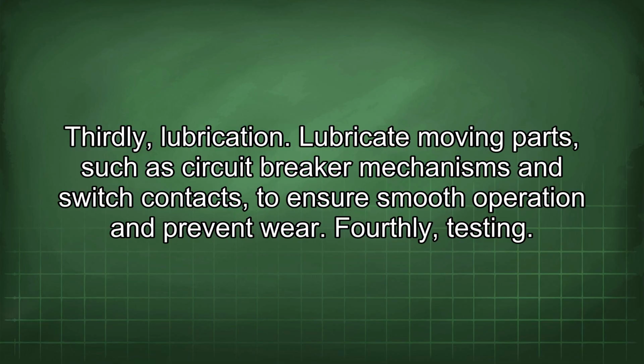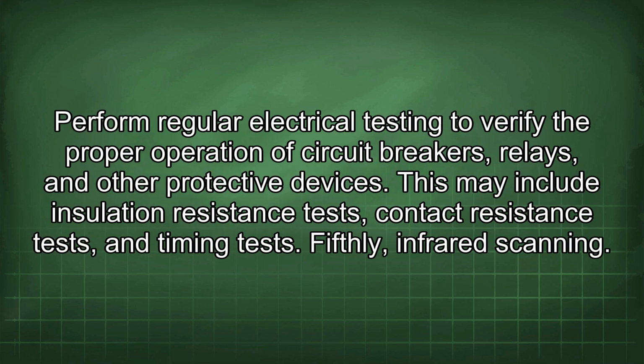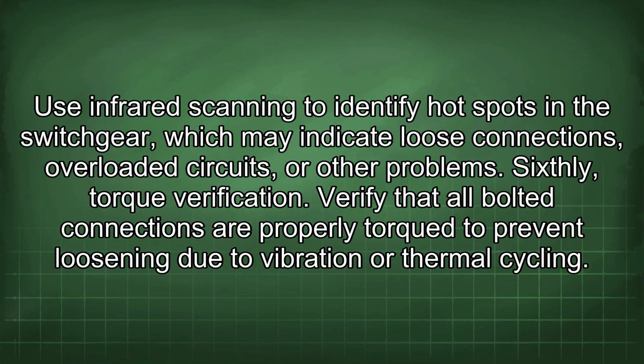Fourthly, testing. Perform regular electrical testing to verify the proper operation of circuit breakers, relays, and other protective devices. This may include insulation resistance tests, contact resistance tests, and timing tests. Fifthly, infrared scanning. Use infrared scanning to identify hotspots in the switchgear, which may indicate loose connections, overloaded circuits, or other problems. Sixthly, torque verification.